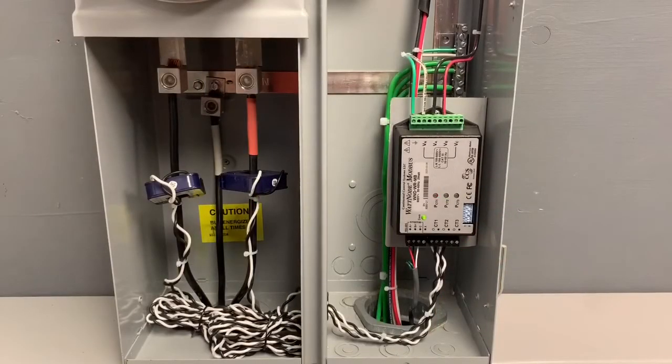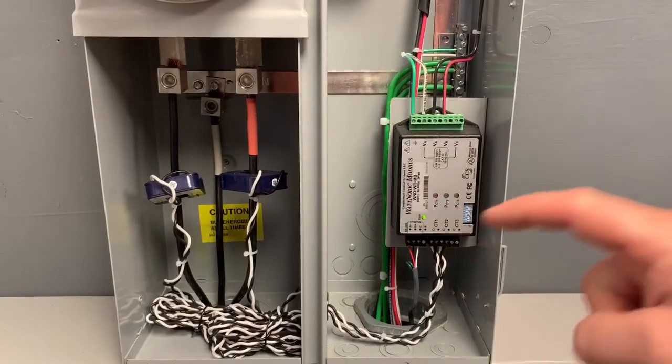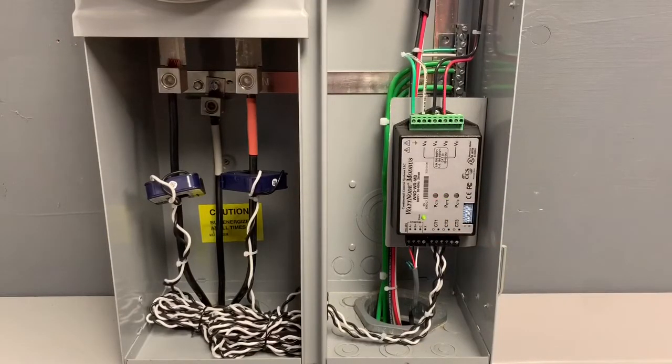Okay, so this is the WattNode made by Continental Control Systems. Down in the lower left corner, this is the Modbus connection that's running back to your gateway. This is allowing the data that's coming off the CTs to come through, be registered, and send that data back so that the XW Pro knows that it needs to regulate its power output for zero export.